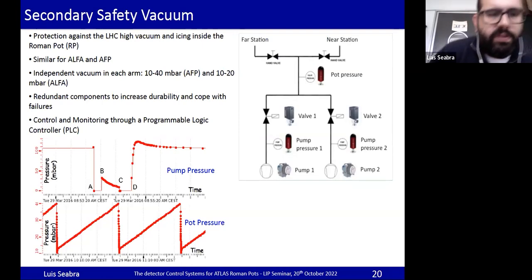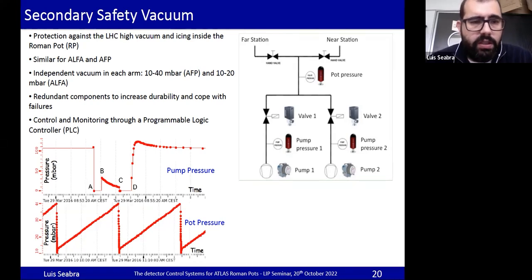For the secondary safety vacuum, it works as a protection against the LHC vacuum and icing. Basically, this is more for AFP, the icing part inside the Roman pot. They are very similar systems, and provide independent vacuum for each arm. For AFP it's between 10 and 40 millibar, and for ALFA between 10 and 20 millibar. It's a duplicated system to increase durability and cope with failures. So I'm showing here pump 1, pump 2, the pressure readout, and the valves as well.